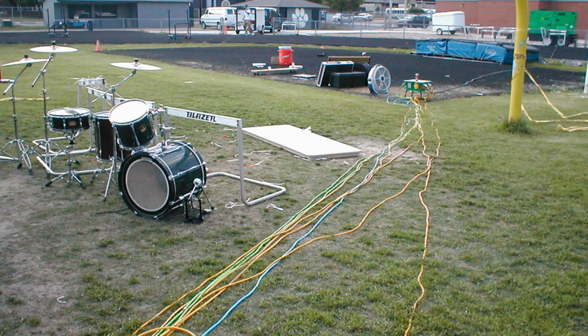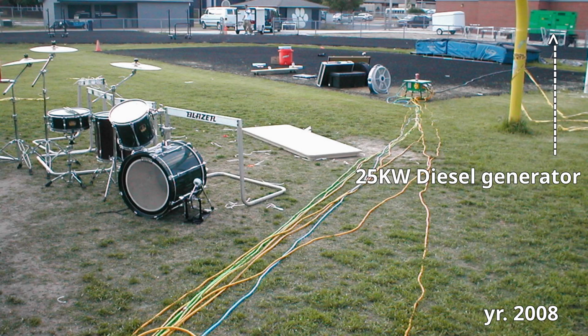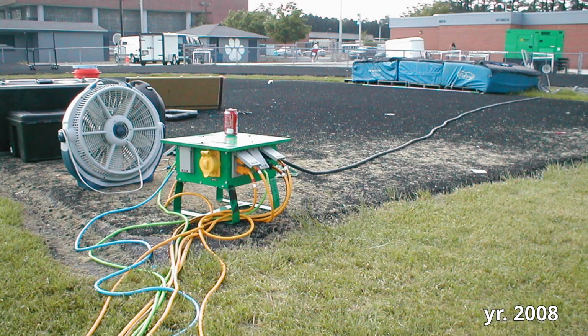We're at a high school set for some rock band type of event, and the generator in the back was about 25 kW. Again, the rental company provided us with a PDU, a breakout box that had, I believe, 6 20 amp circuits on it, and a little 50 amp pass-through. This was more than enough power for this event, and the power cables you see are all 12 gauge, which is more than enough, with a couple of 10 gauge sitting in there too.